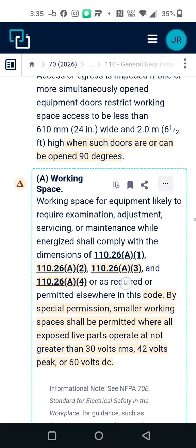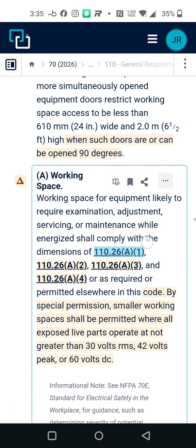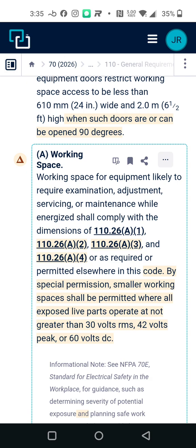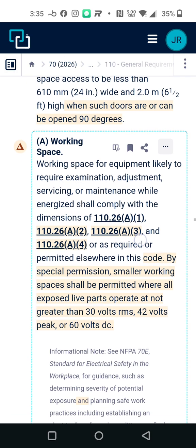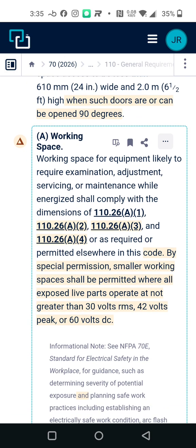Working space for equipment likely to require examination, adjustment, servicing, or maintenance while energized should comply with the dimensions of 110.26(A)(1), 110.26(A)(2), 110.26(A)(3), and 110.26(A)(4), or as required or permitted elsewhere in this code. By special permission, smaller working spaces should be permitted where all exposed live parts operate at not greater than 30 volts RMS, 42 volts peak, or 60 volts DC.